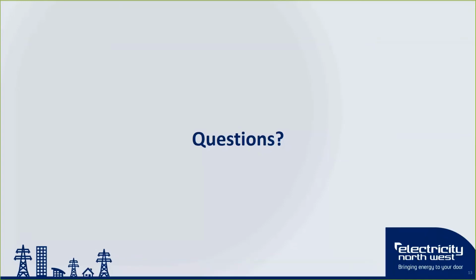Another question that's come through, will ENW carry out a G5 harmonic assessment? If the customer provides us with all the harmonic emission currents, ENW will carry out a stage 1 assessment. A stage 1 assessment is only applicable to LV connections. So if it's a large supply that's on either an existing HV exit point or they require a new HV exit point, we would be in the realms of a stage 2 assessment. But if it's an LV point of connection or an existing LV supply, ENW will carry out a stage 1 assessment in line with ENA engineering recommendation G5.